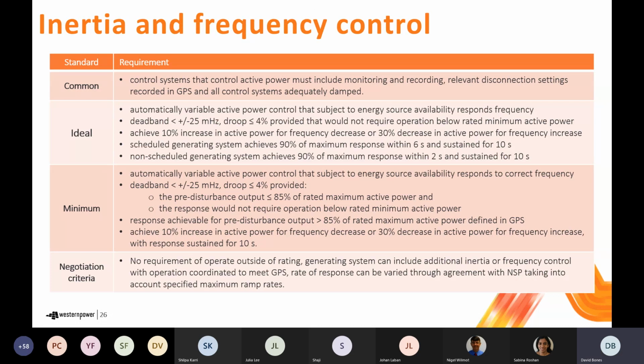The next technical requirement relates to inertia and frequency control. So this is pretty important, particularly for an isolated power system such as this South West Interconnected System, where you want to maintain good control of frequency and frequency stability. And to do that, that's optimally achieved if you've got all generators that can provide a level of primary frequency response actually providing that primary frequency response. And that's what this requirement seeks to achieve.